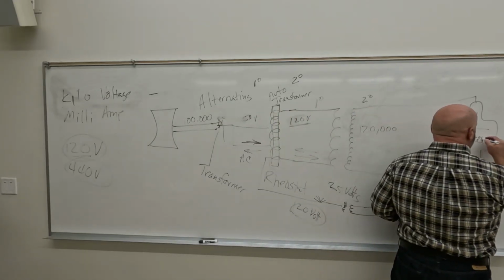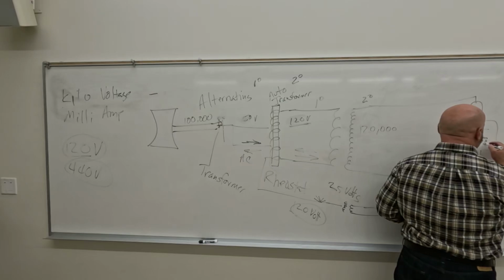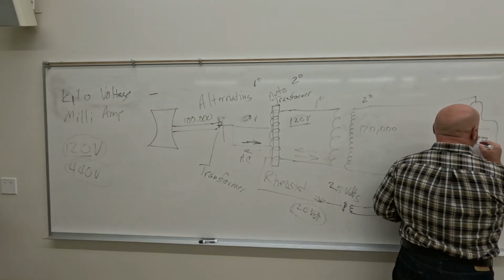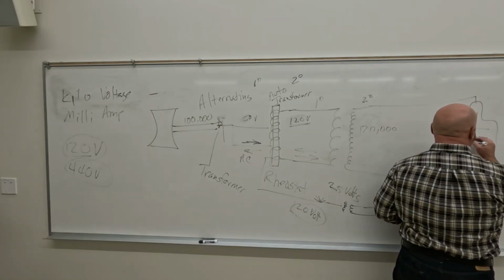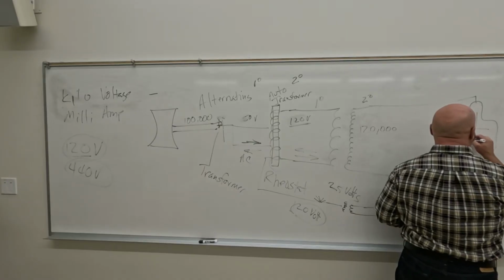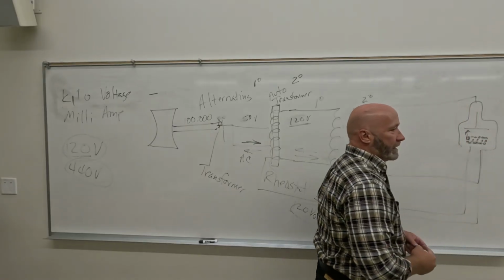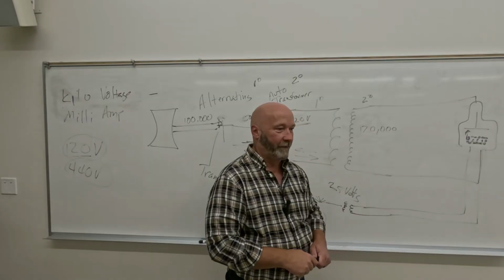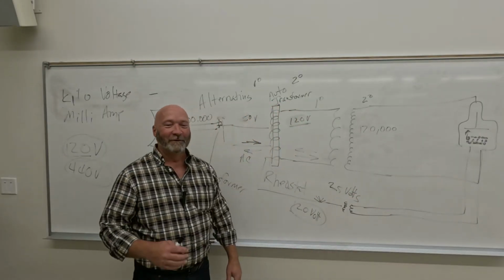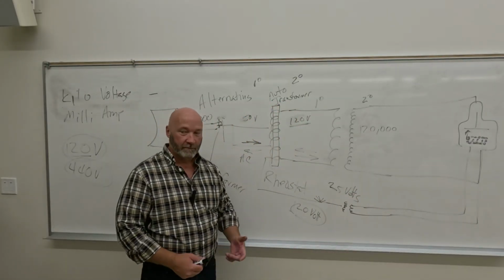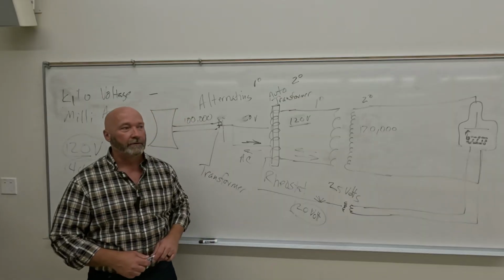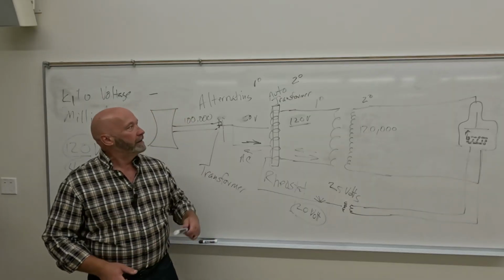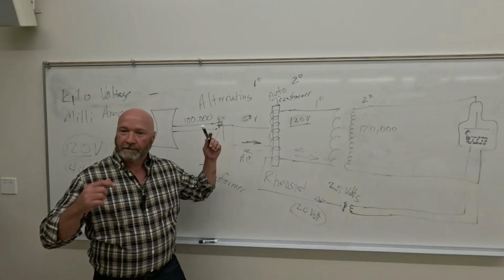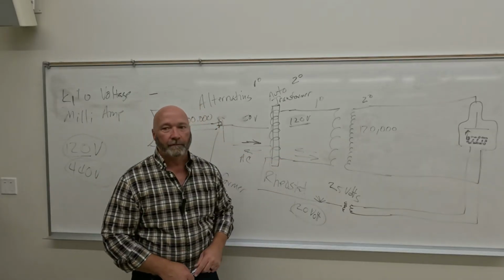electrons that collected to make your filament hot travel across the X-ray tube at really fast speeds. How fast? Really fast. Very good. It's a miniature lightning bolt. That is exactly what it is. What controls the speed is your voltage. The higher the voltage, the faster they go across the X-ray tube.